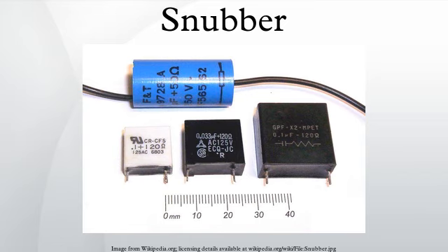Inductive elements are often unintentional, but arise from the current loops implied by physical circuitry. While current switching is everywhere, snubbers will generally only be required where a major current path is switched, such as in power supplies. Snubbers are also often used to prevent arcing across the contacts of relays and switches, and the electrical interference and welding or sticking of the contacts that can occur.